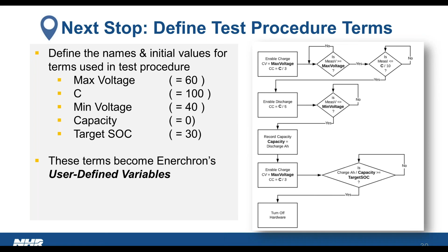If we look into the flowchart, there are a number of terms: the maximum voltage, which depends on the battery pack, or C, the total capacity assumed for the battery—is it a 100 amp hour battery, or a 10 amp hour battery? What is that initial value estimated? What's the minimum voltage, how far down can I go? We'll need a place to store capacity when we record the number of amp hours, and then use that in the formula to say where we want to get—30% full or 50% full?